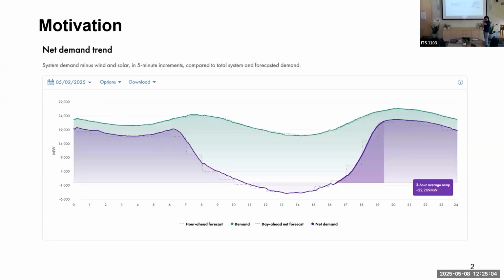Well, that's some motivation here. I think everyone here has seen some version of this, but this is a CAISO load and net load chart from May 2nd of this month. If you look at that 4 to 9, or maybe 5 to 9, period, they have a 3-hour average ramp up of around 22,000 megawatts. And this is all non-solar, or maybe non-renewable as well. And this has to come online within 3 hours. So this puts a lot of stress on the grid and on the generation infrastructure. You need to have these assets available and ready to go at all times. And you also have to keep your spinning reserves throughout the day, which is another source of inefficiency on your grid when you don't need them during most of the daytime.